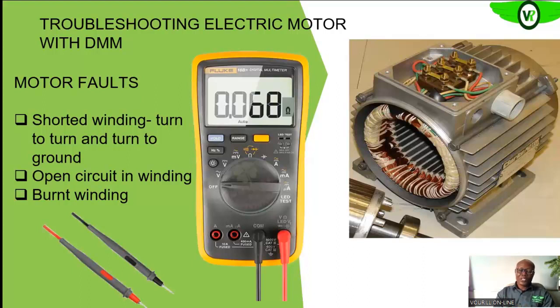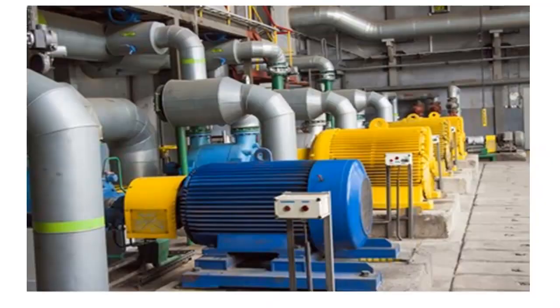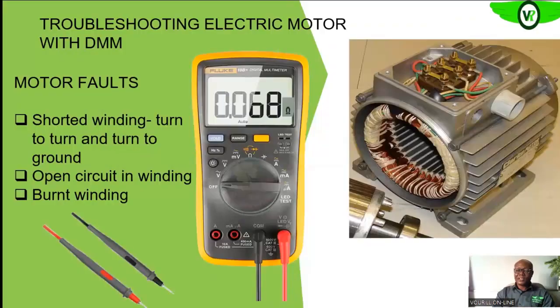Now, the tests that you carry out on the electric motor are all dead tests, that is, when the motor is inactive. Remember, you tested the control and the power circuit to the point of the motor and have confirmed that the power circuit and the control circuit are okay. Now you have been able to identify that the problem is with your electric motor. There are a few tests that you can do right there in the field, and there are some that, once you have ascertained what the problem is, require you to loose that electric motor and take it to the workshop to carry out further tests and then maintain the electric motor accordingly.